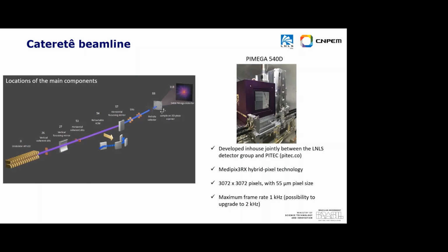That is enough to study a lot of different materials, colloids, gels, different systems. And for the slower rates, we do not have a limit. It will depend on your sample, how long the sample can take radiation. So if it's really slow dynamics, for example, a glass, but usually glasses are quite resistant to radiation damage, so it's not a problem. You could measure for minutes, hours, there's no limit, but the fastest we can go is 1 kilohertz.